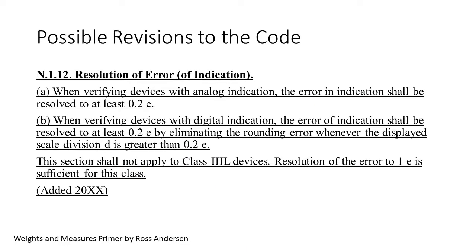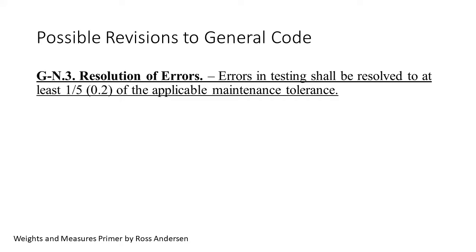This is the proposed addition to the test notes in Handbook 44 to clarify that the error has to be resolved to at least .2e parallel to R76. It addresses both analog and digital as just explained to assure equivalency. I'll explain the Class 3L in Part 3. The resolution of error is not just a scales code issue. I might suggest it ought to be addressed more generally. This proposed Section GN3 creates a 1-5th rule for the resolution of the error in the general code to go with the 1-3rd rule regarding the accuracy of the standard. It specifies that the errors in testing be resolved to at least 1-5th of the maintenance tolerance. Note the 1-5th rule is relative to maintenance tolerance while the 1-3rd rule is relative to acceptance tolerance. It could also go in the fundamental considerations.